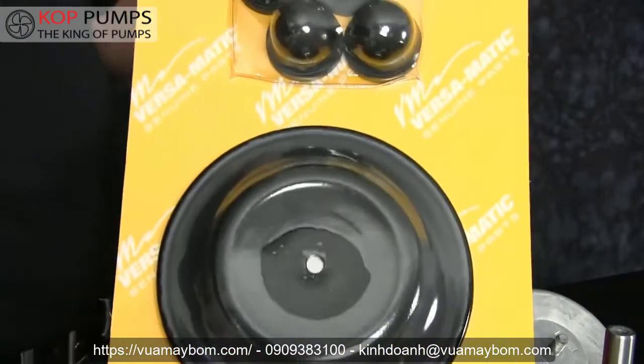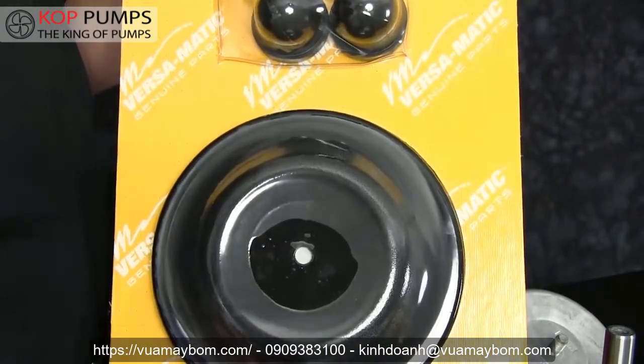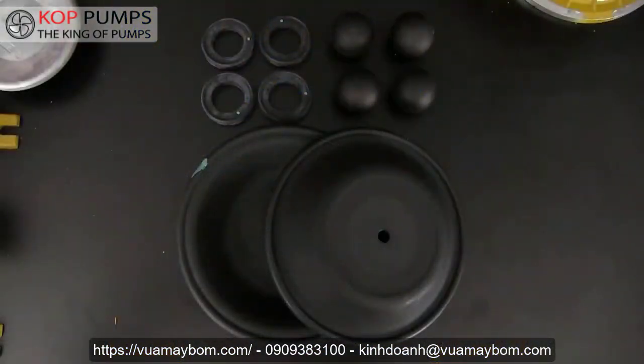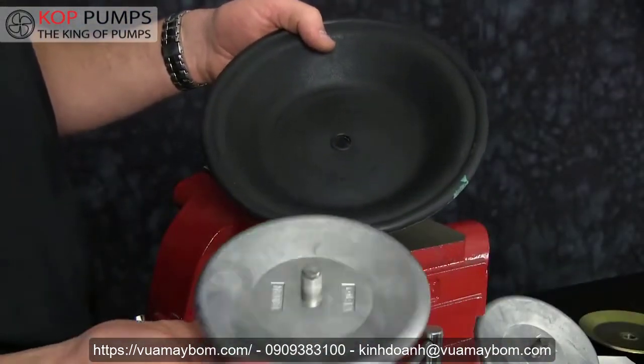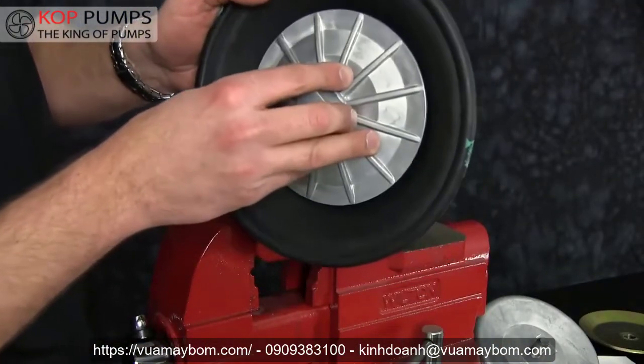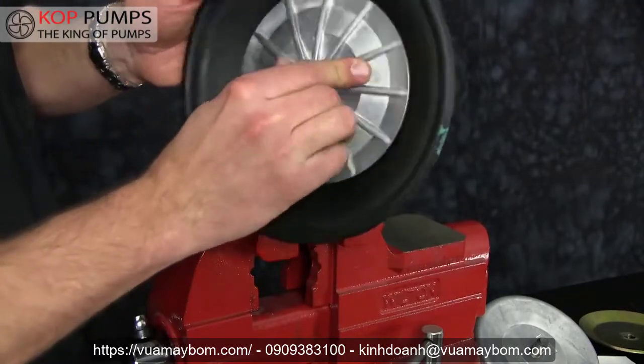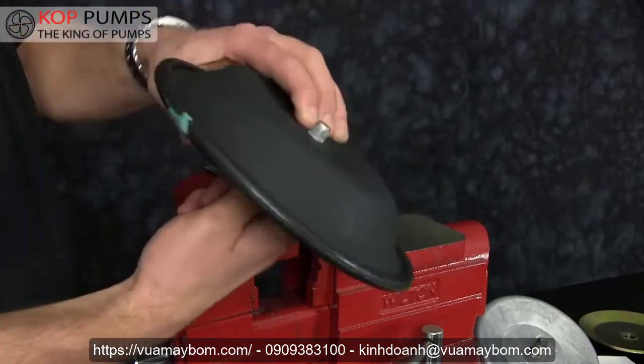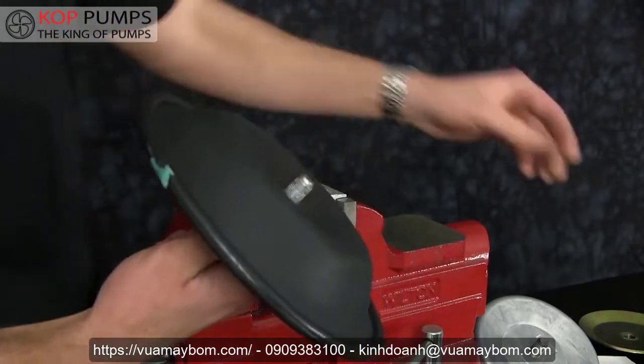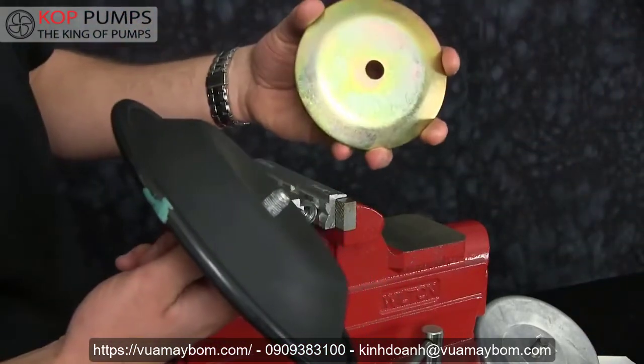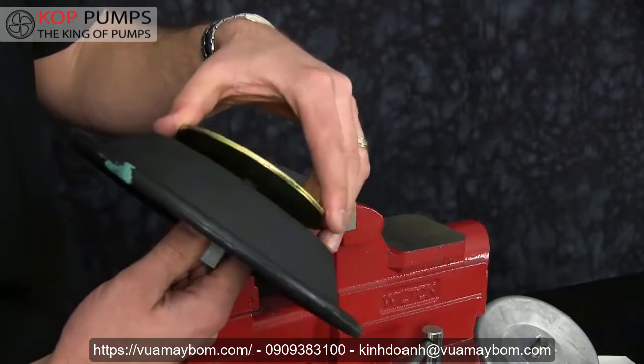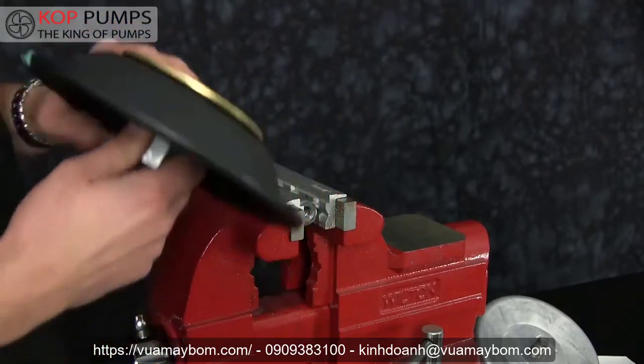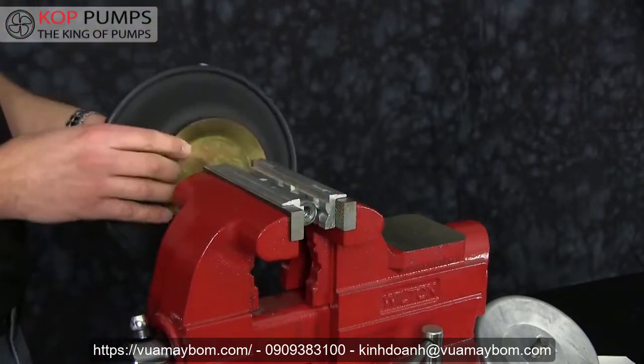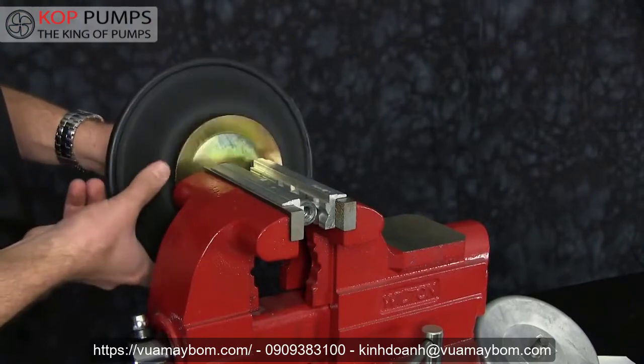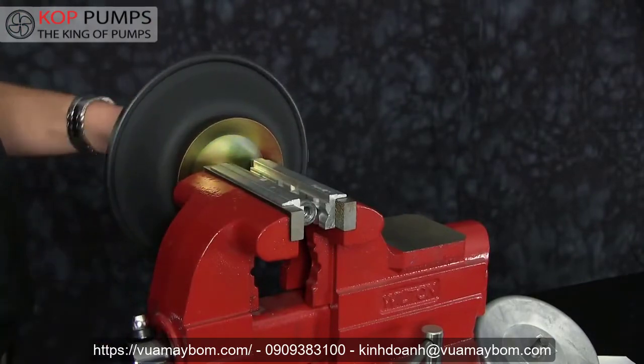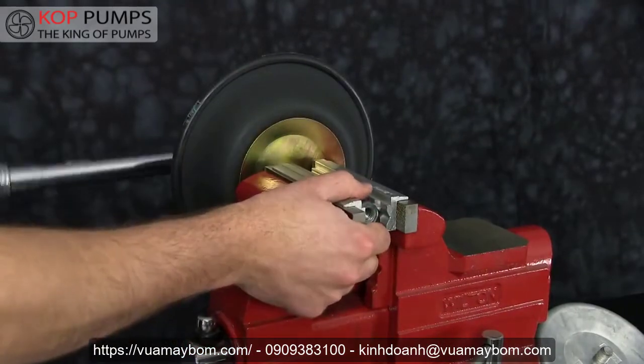Now we're ready to install our wet end kit. Note the orientation of the diaphragm, with the natural bulge in. Install our outer diaphragm plate and our inner diaphragm plate with the radiuses of both plates facing towards the diaphragm. Be sure to torque the diaphragm assembly to the recommended torque spec in the service manual.